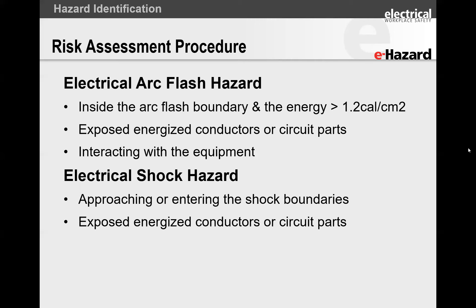The other electrical arc flash hazard is when you have exposed energized conductors. You need to make sure that you have enough energy to cause serious burns. The second condition is exposed energized circuit parts, and the third is when you are interacting with equipment — opening up a cover, opening a door, removing a cover, switching something on or off, racking in a breaker, or racking out a breaker. If all of these terms are foreign to you, please don't be intimidated. Your electricians and plant operators understand this terminology.